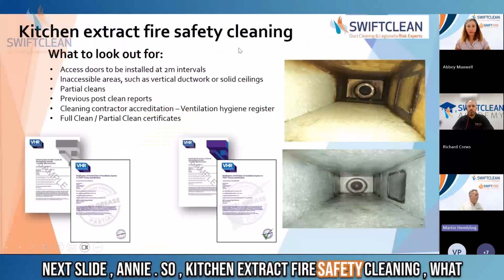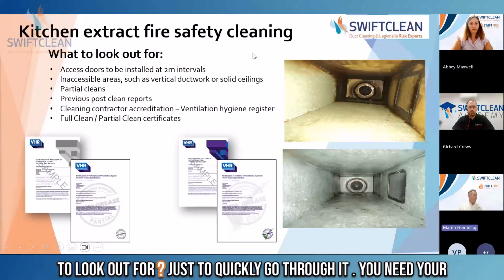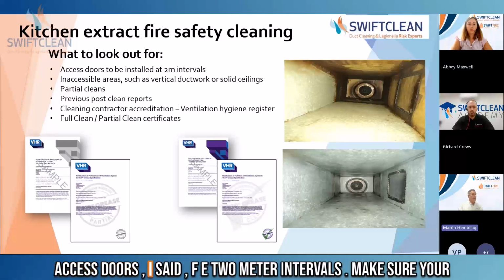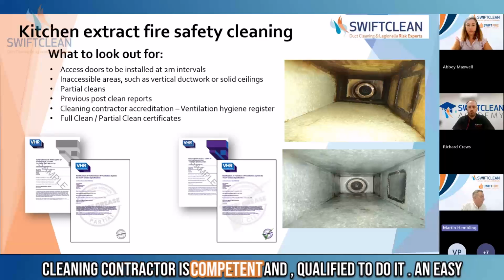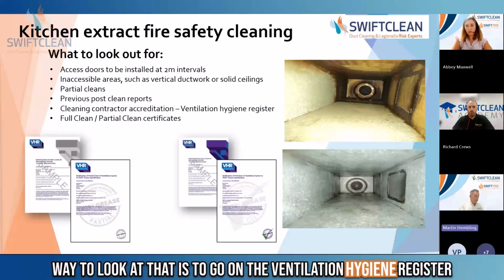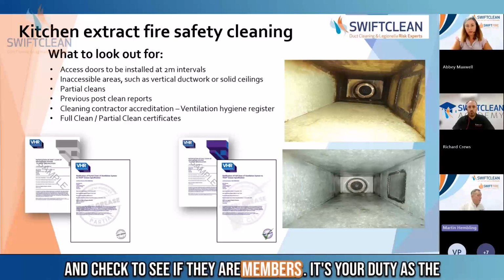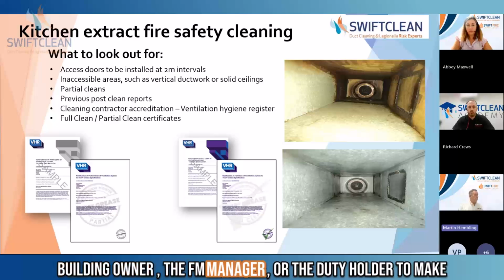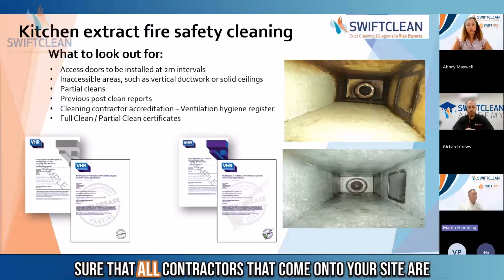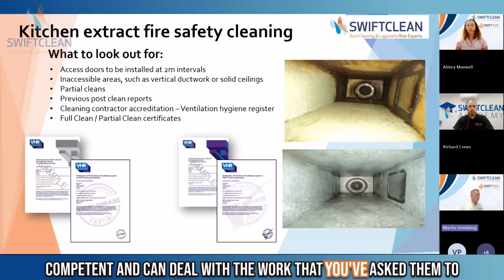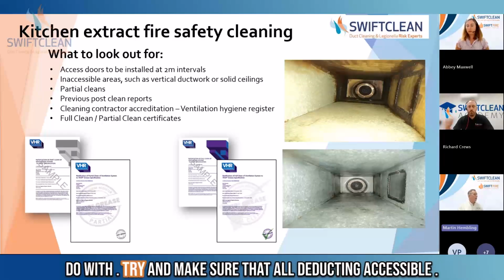So, kitchen extract fire safety cleaning, what to look out for - quickly going through: you need access doors every 2 metre intervals. Make sure your cleaning contractor is competent and qualified to do it. An easy way to check is to go on the ventilation hygiene register and see if they're members. It's your duty as the building owner, FM manager, or duty holder to make sure all contractors coming onto your site are competent and can deal with the work you've asked them to do. Try to make sure all the ducting is accessible.